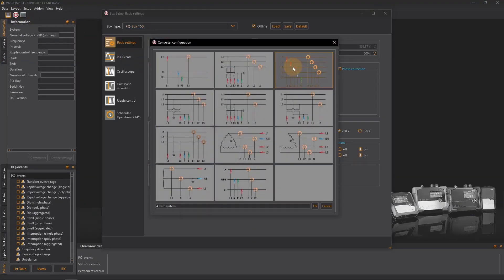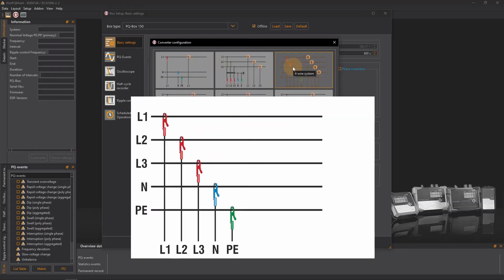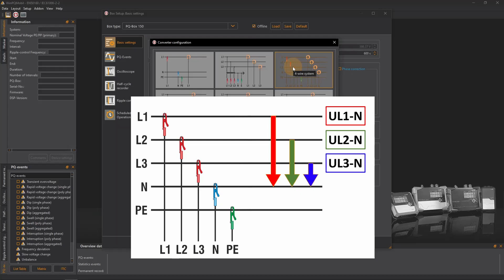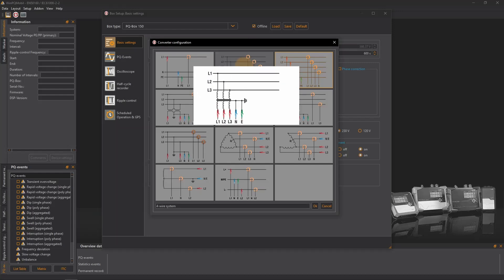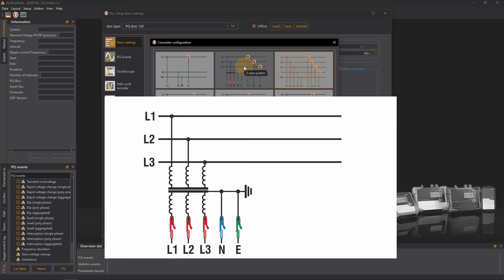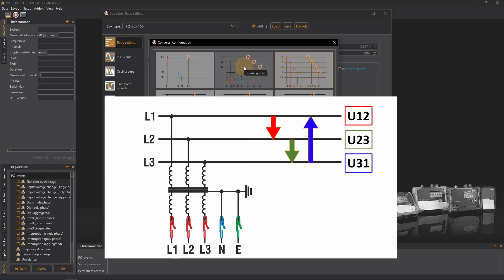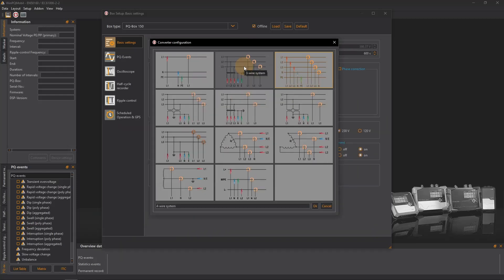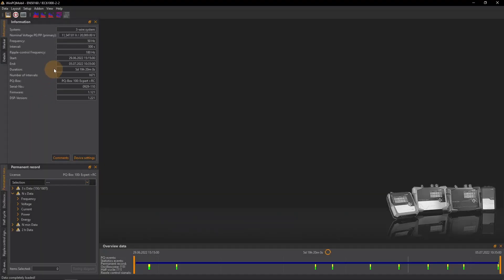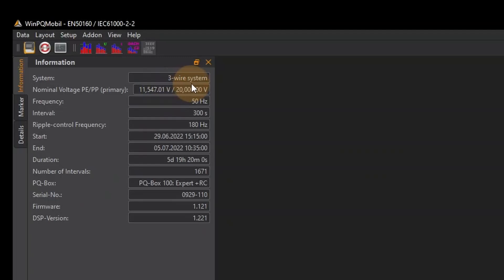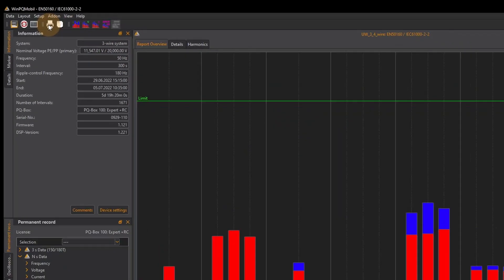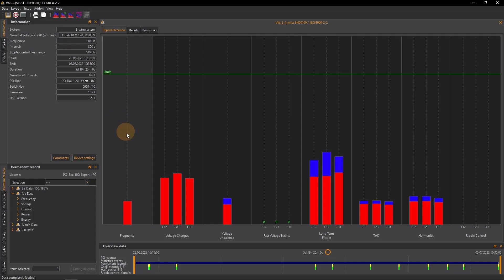In a classic 4 wire system configuration in the low voltage grid the PQ box evaluates the voltages between the line conductor and neutral conductor. In a 3 wire system however which is common in medium voltage grids it evaluates the line to line voltages. Consequently only the evaluated line to line values appear in the report as here in a measurement in the medium voltage grid.